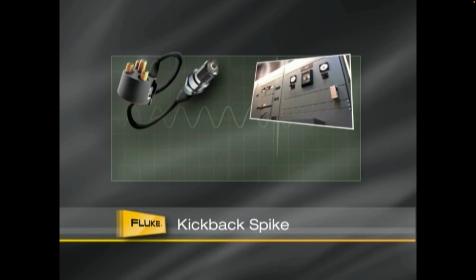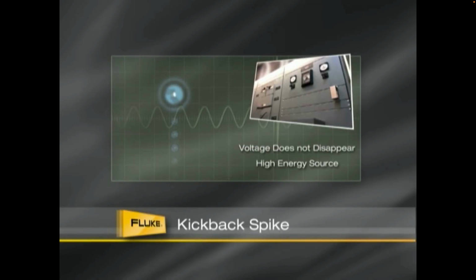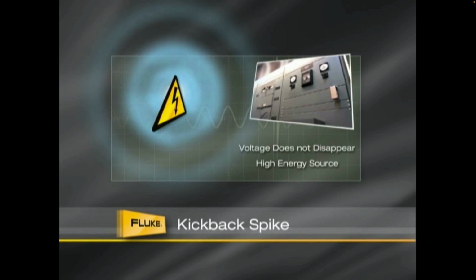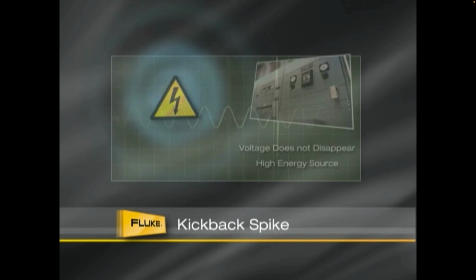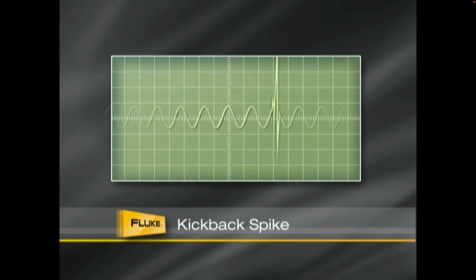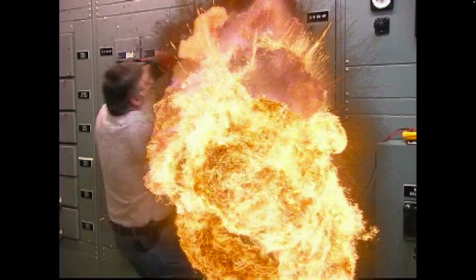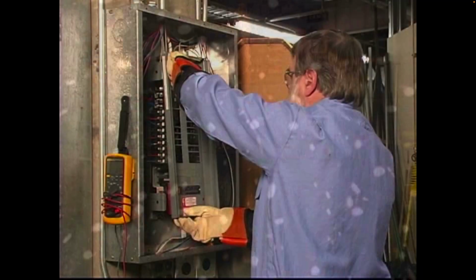And here's why. In your car's ignition, the power source is weak and the spark disappears as soon as the voltage does. But in a power system, the system voltage does not disappear, and because the circuit is a high energy source, it can supply current to the spark until the surrounding air breaks down into a conductive plasma, causing a major fault. When transients ride on top of the system voltages that supply industrial loads, they can reach thousands of volts, and the consequences can be devastating, particularly for anyone taking measurements on electrical equipment.